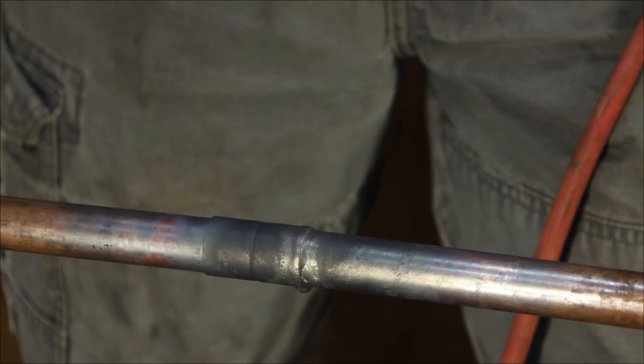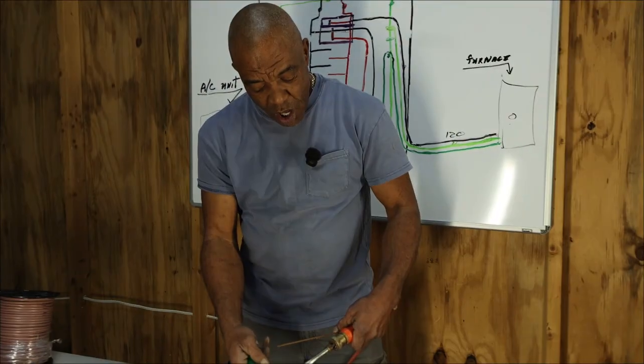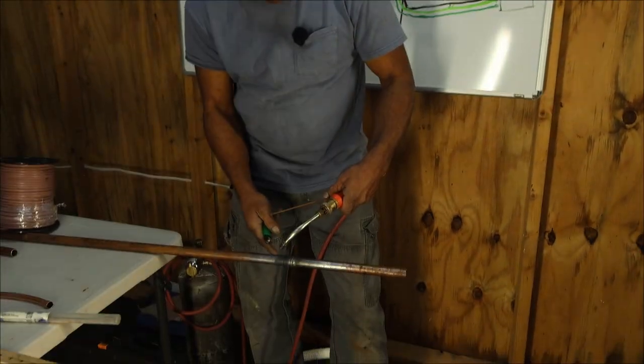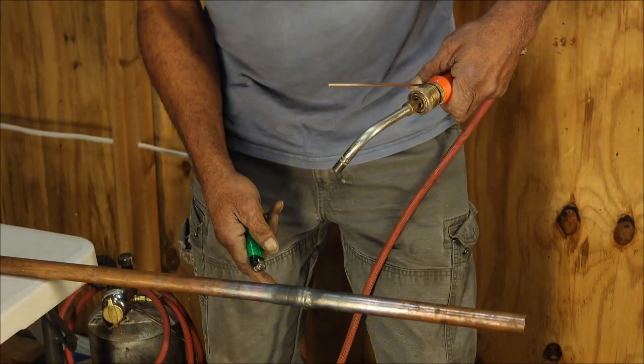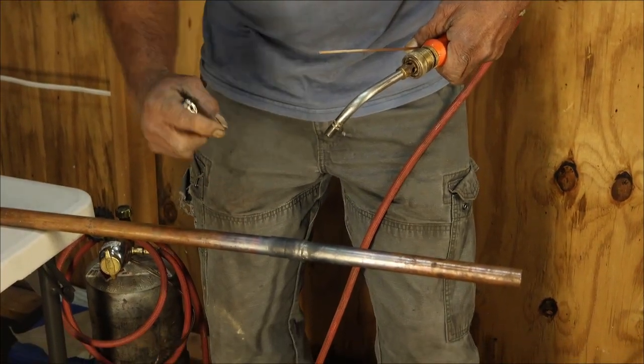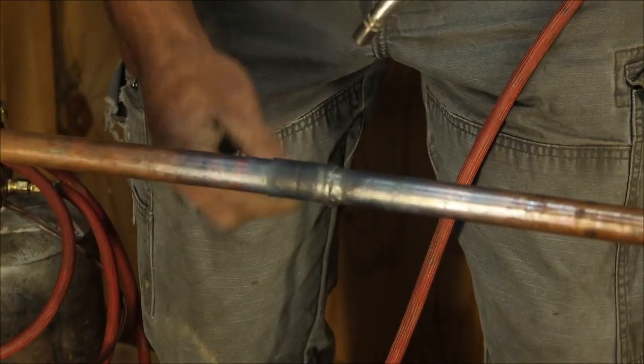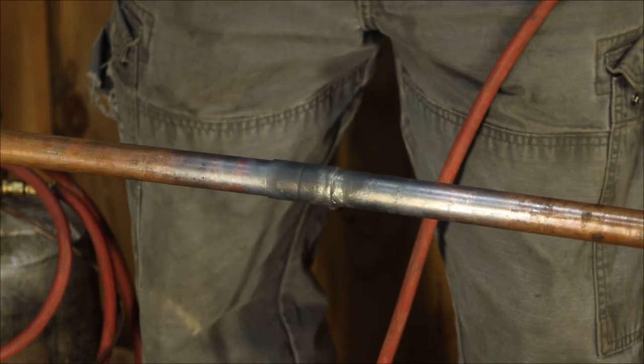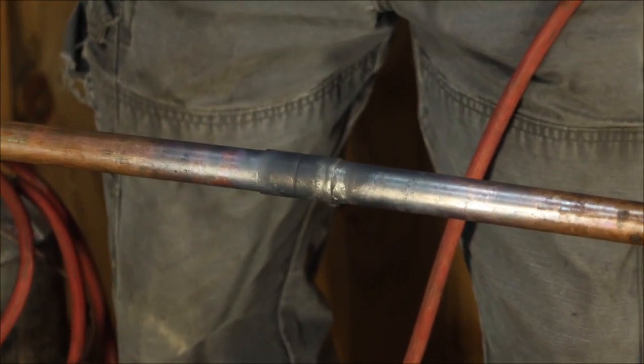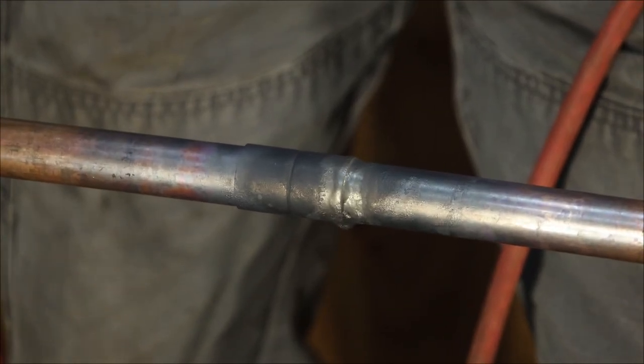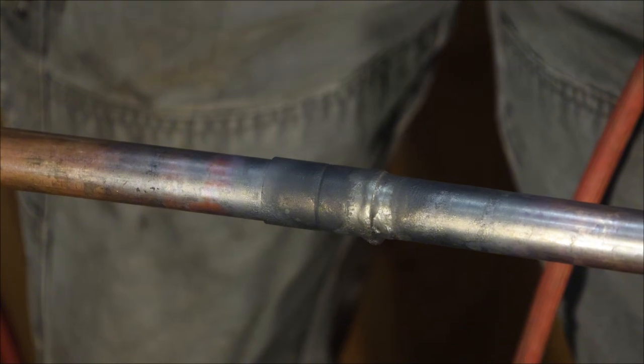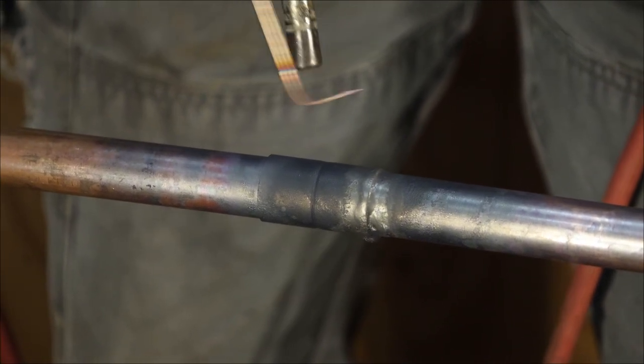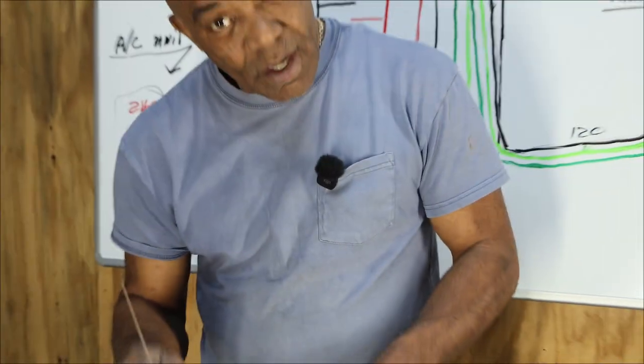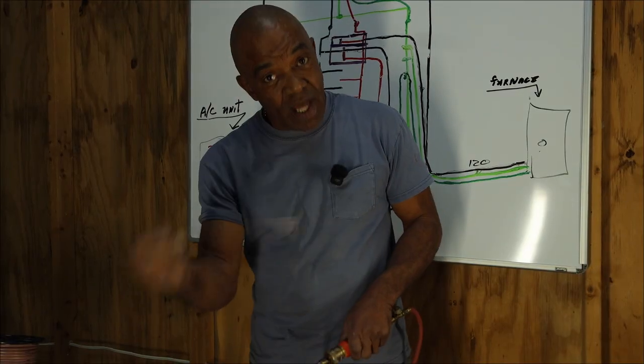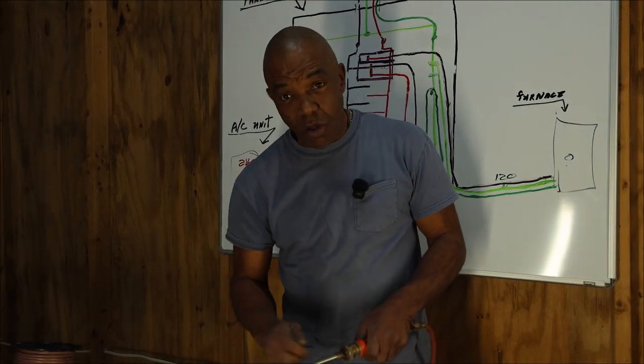I don't want the pipe too hot. You will have to kind of see when the brazing rod is running too fast, running like water. Back your heat off so that you're not applying as much, so that you get a good coat of the brazing without it running too fast. This takes a little bit of technique, and that technique has to be learned, has to be practiced. But if you follow these principles, this theory, practice, follow this application as I'm teaching it, it won't take you long and you'll be good at it.